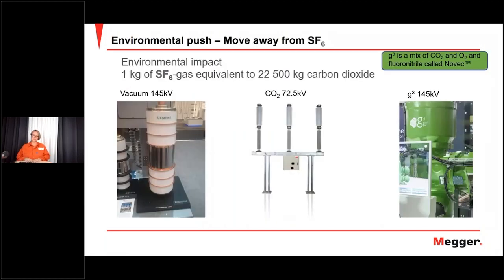But SF6 is a trouble, right? It's very bad for the environment. And that's why we today try to work with higher voltages also on the vacuum breaker. So Siemens has one for 145, and I have heard that in Asia they even have higher voltages for vacuum circuit breakers. I haven't seen them at all, but this kind of development, of course, they are chasing each other, the different manufacturers. On outdoor breakers, they also try to use other gases. So we have CO2 up to 72 kV. And we also have a gas here, as you see to the left, right, sorry. It's G3, which is a mixed gas.